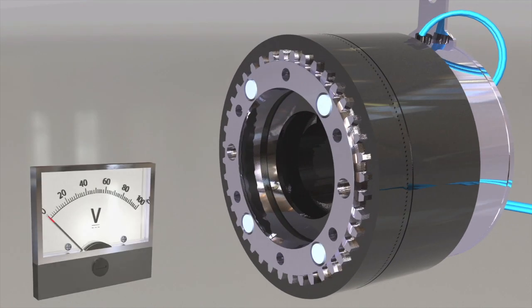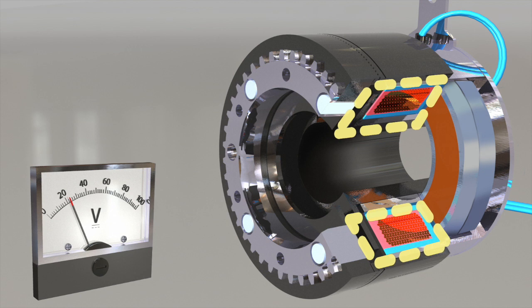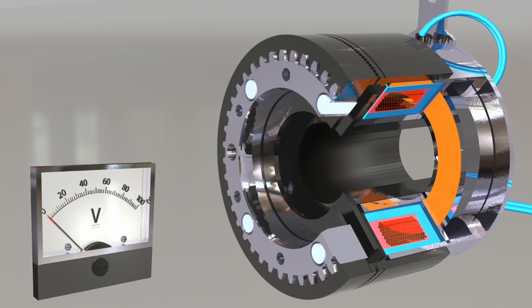This flux is then transferred through the small air gap between the field and the rotor. The rotor portion of the clutch becomes magnetized and sets up a magnetic loop, which attracts the armature teeth to the rotor teeth. As soon as the armature and rotor are engaged, torque transfer is 100% efficient and there is no slippage.